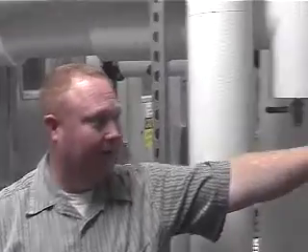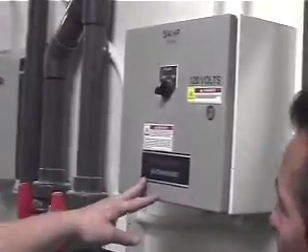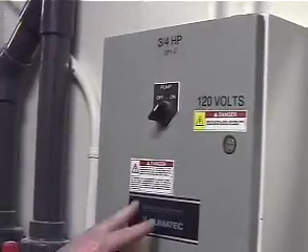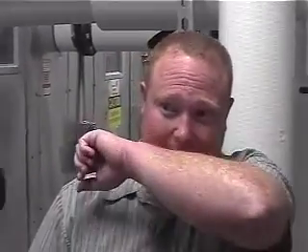This right here is your pump control. What we do is we enable the pump on and off for your evap section. It does have a low level sensor in it. It's a sensor that says that if it gets below this, it disables the pump from running. So that evap pump, if you get an alarm that says the status doesn't match the command, there's a good chance you might not have any water in it.